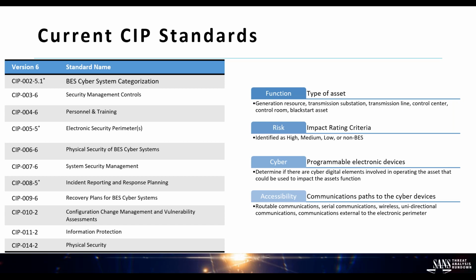The primary reason, again, is they are not built to be a security device - they're built to be an operational asset. So every cycle, every scan rate, every processor second matters in these real-time operating system, industrial control system devices. Peeling off any of that capability to do some level of security packet inspection or check prior to doing what they're built for could cause a safety event, could cause equipment damage, could cause a human loss of life issue. So the vendors of those devices specifically look to the asset owner to secure around the device - meaning with appropriate perimeters, appropriate controls, appropriate access, physical, cyber, all of the above.